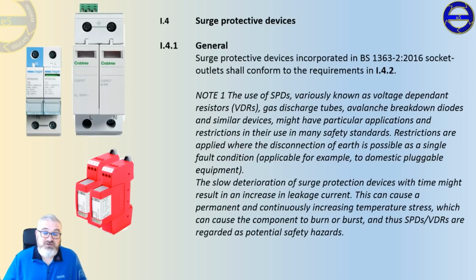Now, the slow deterioration of surge protections with time might result in an increased leakage current. Now, we all know electrical installations with modern electronics all leak to earth. The old TFT monitors used to leak 3.5 milliamps. If the easiest way of checking is put a very sensitive clamp meter on your main DNO earth, you'll probably see that you get some small amount of current. On major installations, I've measured leakage current in the tens of amps before from connected power transformers, power electronics, lots of waste leakage in poorly constructed and inefficient equipment.